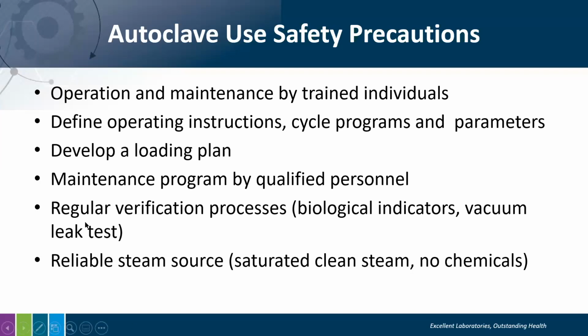Also, for pre-vac autoclaves, and actually for any type of autoclave, it is important that the source of steam is clean steam. We are talking about decontamination of waste, but in some cases an autoclave can be used for sterilization, and that's even more reason the saturated steam must be clean, with no chemicals inside the autoclave. Next slide.